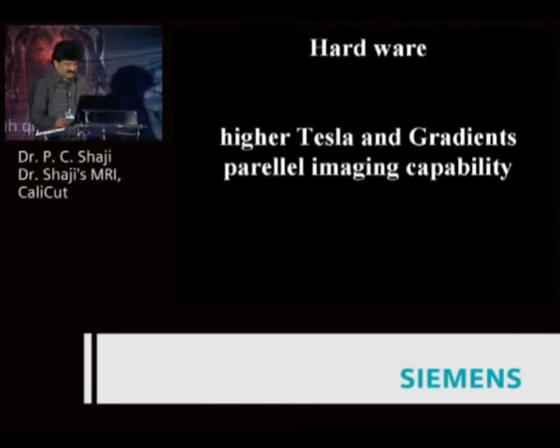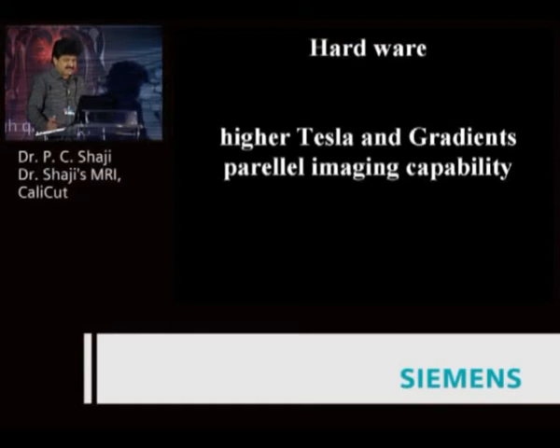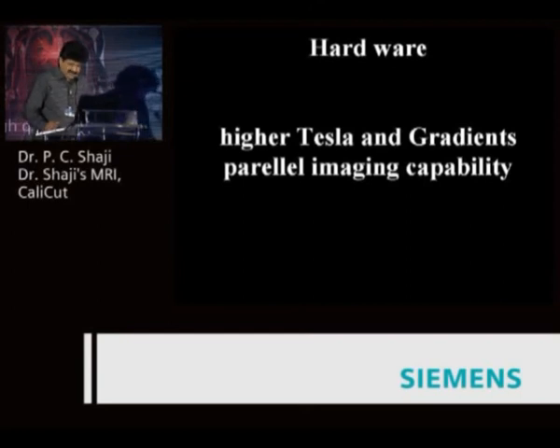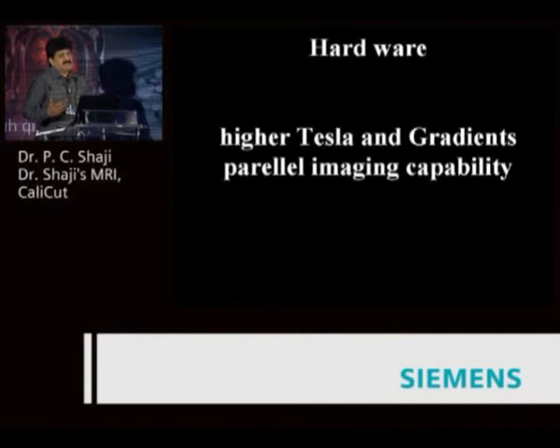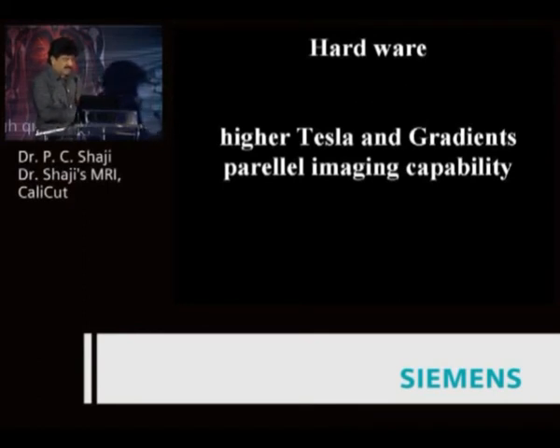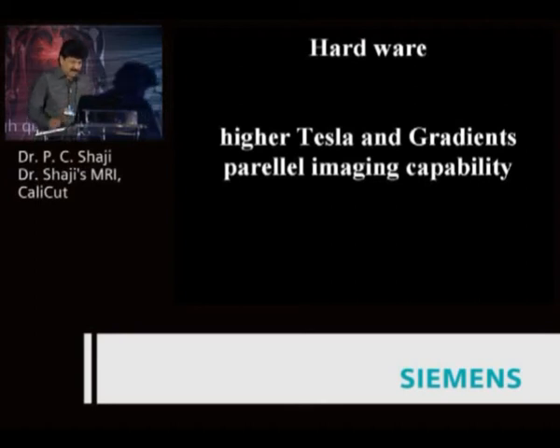Regarding hardware, it is well known that higher Tesla gives better SNR, and with high-performing gradients you get a shorter TR and TE. Parallel imaging techniques are excellent — you can combine elements and get faster scans. If you ask me, if you have a 3 Tesla system without parallel imaging versus a 1.5 Tesla with parallel imaging, I personally prefer the 1.5 Tesla with parallel imaging.